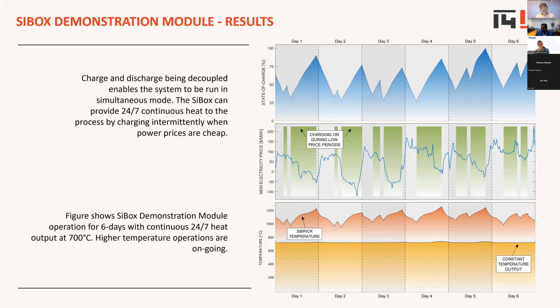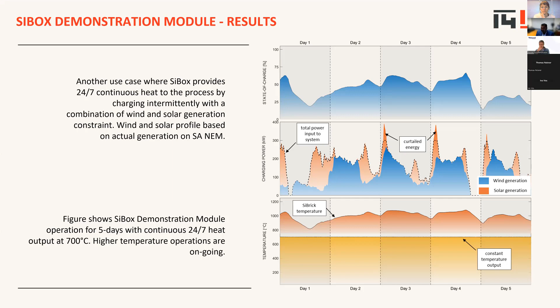On that renewables point, this is another test with a combined solar plus wind generation profile. The orange is the solar profile and the blue is the wind profile. Using just the renewable profile, the system charges and maintains its state of charge so it can deliver a constant high temperature output from the box. This was a 5-day continuous run we finished recently. The wind and solar profiles are based on actual generation from the South Australian national electricity market, not location specific, but for the entire state.